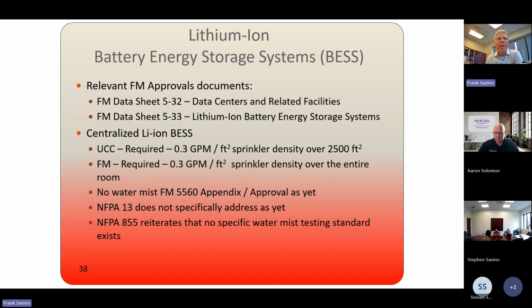Right now, there is no Factory Mutual appendix for this hazard, for battery energy storage rooms, central storage. NFPA 13 does not specifically address this yet. And NFPA 855 reiterates that no specific water mist testing standard exists.